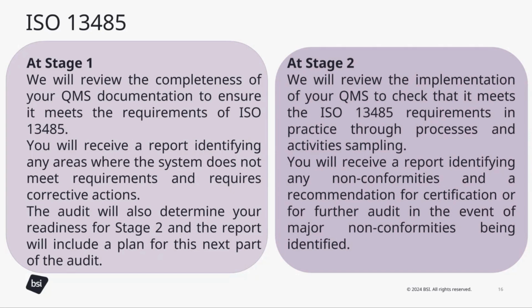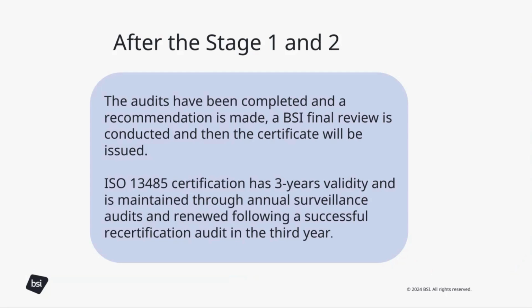In stage 2, we will review the implementation of the quality management system and check that it meets the ISO 13485 requirements in practice, through processes and activities sampling. So this is stage 1, and stage 2 is also part of the ISO 13485, and you will receive, of course, a report to identify any non-conformity and a recommendation for the certification. So once this has been completed, we have a recommendation. And then the final BSI review is conducted, and then this is when we will issue a certificate.